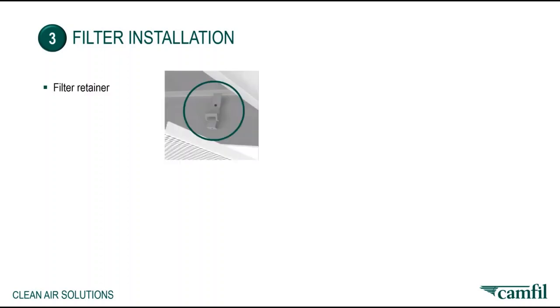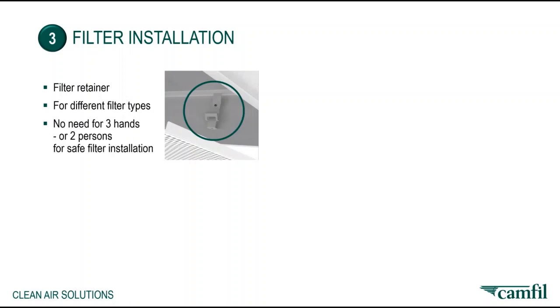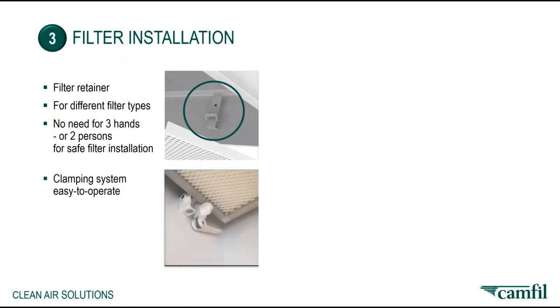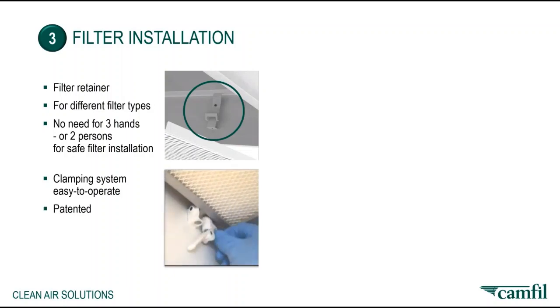Point three, filter installation. Filter retainers are a very useful feature here, and should ideally be adjustable for different filter types. We've seen the issue of filter sealing. There's no need for three hands, more realistically two persons, for safe filter installation that way. Then the clamping system itself should be easy to operate. With CleanSeal, this is patented and of course toolless.